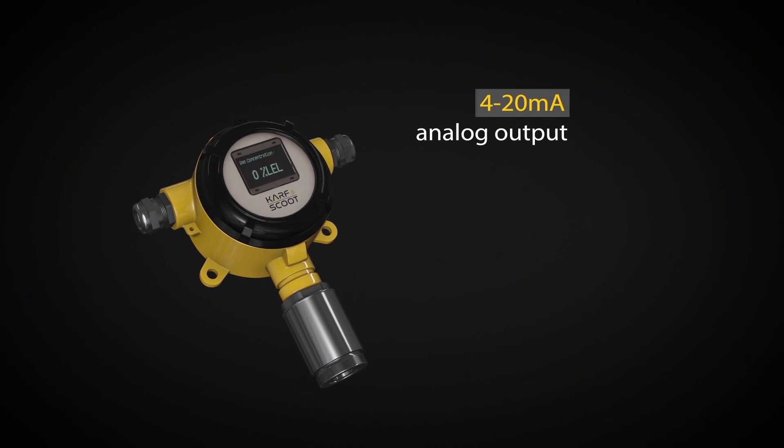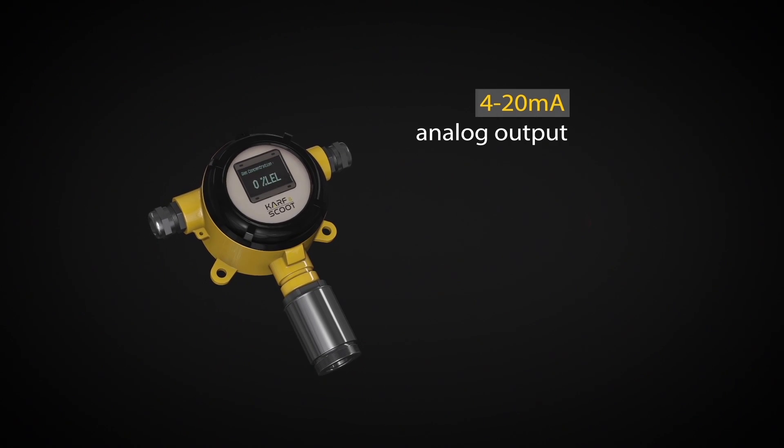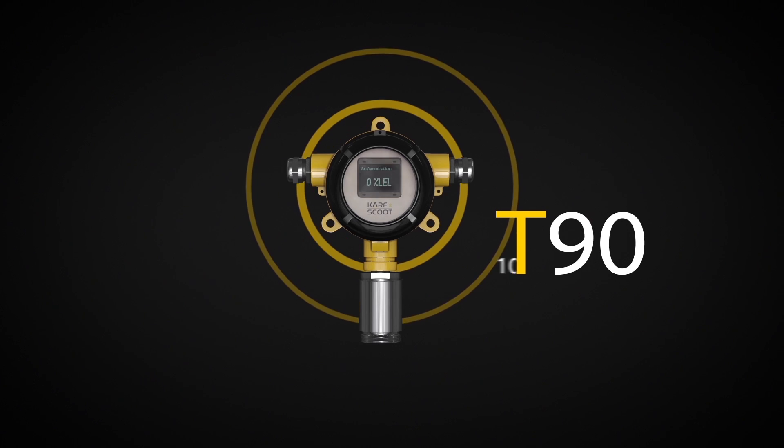4-20mA analog output connects Karf Scoot to industrial systems, while the two relay outputs enable emergency stop of the whole system when there's a gas leak. T90 reaction time is less than 10 seconds in case of a gas leak.